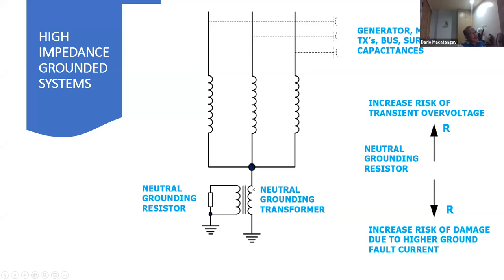So if you divide this by the PT ratio here, you have a certain voltage here, secondary voltage, that can trigger your 59N, which is a voltage sensitive relay. When it sees a voltage higher than its pickup, we call it the minimum voltage that it will trip, then it's going to trip. And sometimes it has a time delay. You can introduce time delay there. Of course, you need to introduce time delay in those set points because you don't want a nuisance trip, okay?